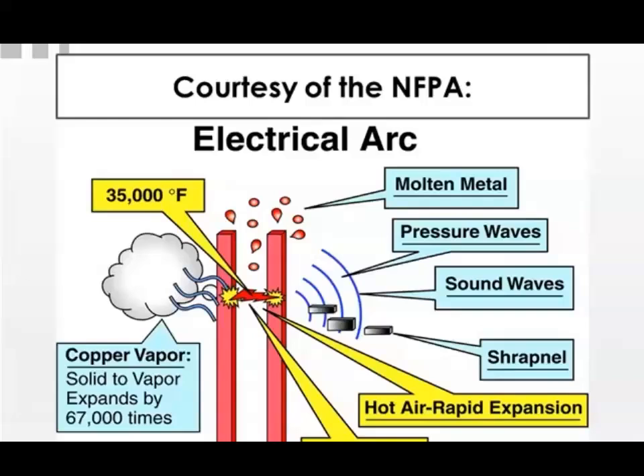So when an arc flash or an arc blast occurs, you have temperatures that reach 35,000 degrees. Again, it vaporizes any material known to man or woman. You've got molten metal coming out at you. You've got pressure waves coming out at you. Sound waves. Obviously burns are the most catastrophic event, but people have blown eardrums because of the severity of the shock waves and the sound waves. Pardon me, you get shrapnel coming at you. Hot, rapid air expansion, very intense light, and copper vapor.